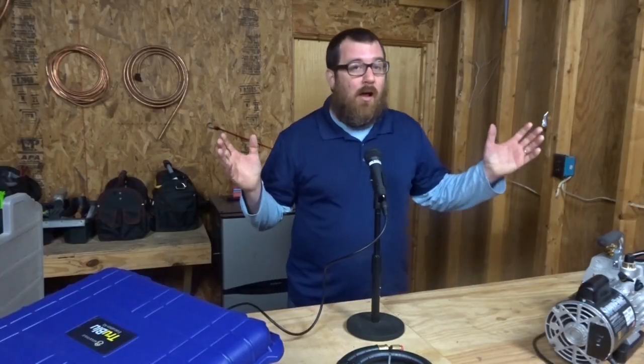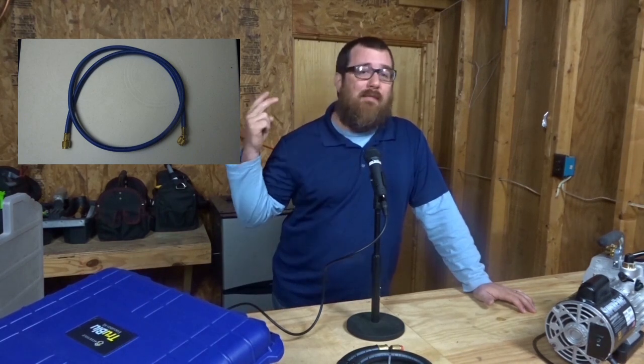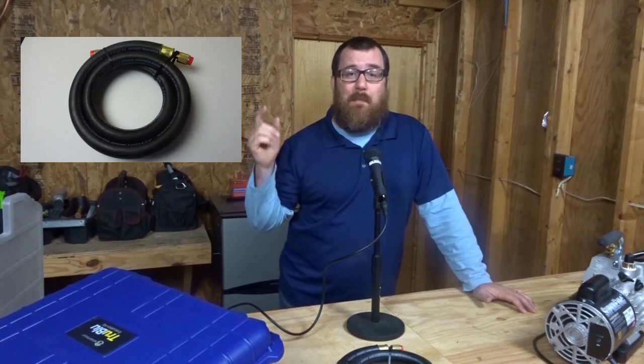We're gonna talk about HVAC vacuum — which vacuum hose is the best. I pit four different hoses against each other in a vacuum challenge: a regular gauge hose, a 3/8 Yellow Jacket vacuum hose that's about six years old, a brand new Appion half-inch vacuum hose, and the lord of them all — the TruBlu hose. We're gonna run them for 30 minutes side by side to see what ultimate vacuum we can reach.